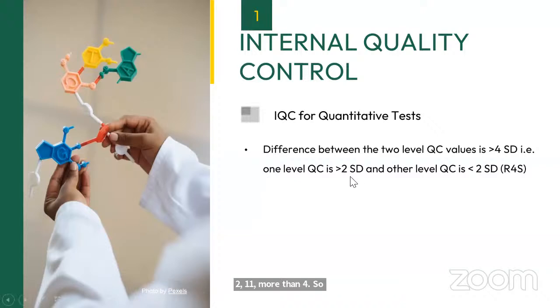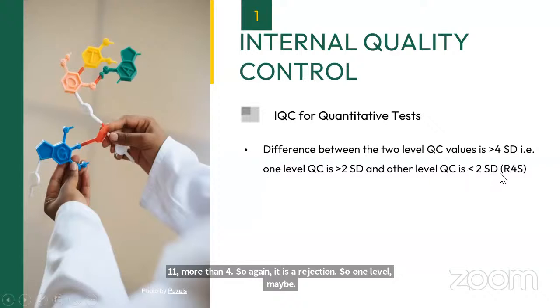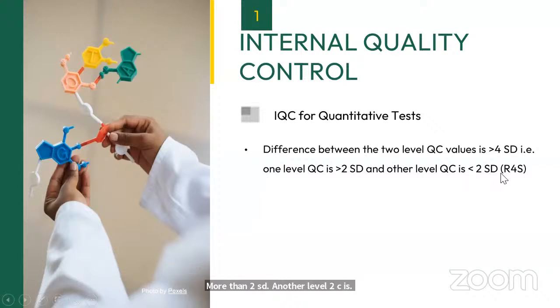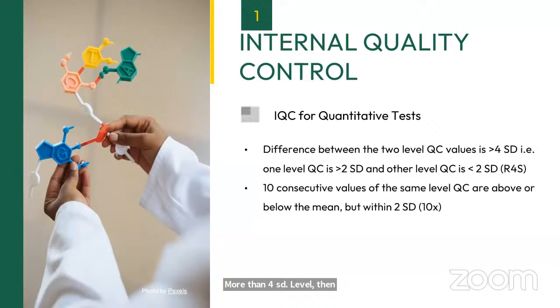So one level may be more than 2SD and the other level less than 2SD. That is R4S. We call it the R-4S rule. So whenever the difference between the two levels of QC is more than 4SD, it is a rejection rule. Again, 10 consecutive values for any one level is a rejection. This is the same rule which we have seen for one level of QC, so the same rule applies for two levels of QC also.